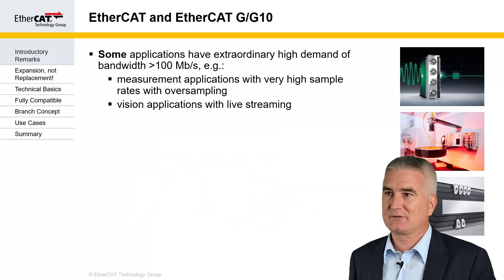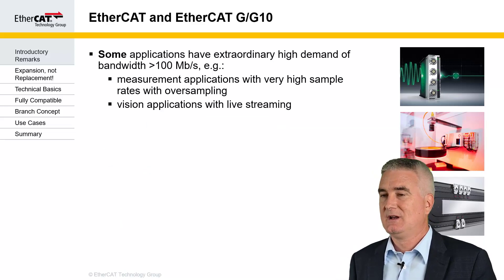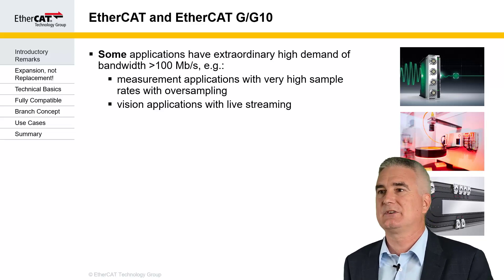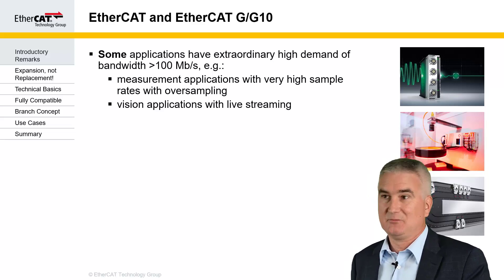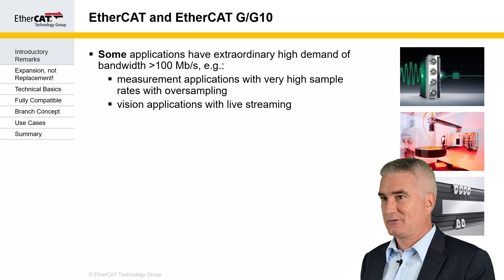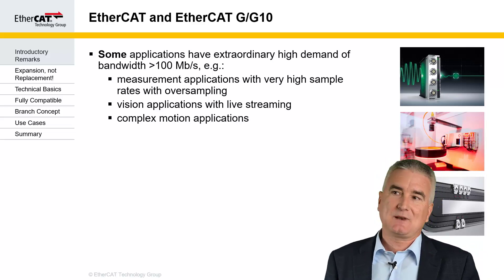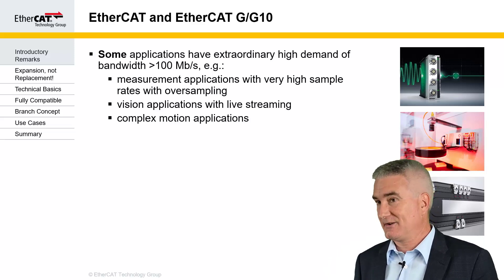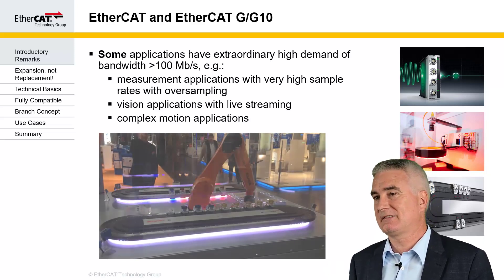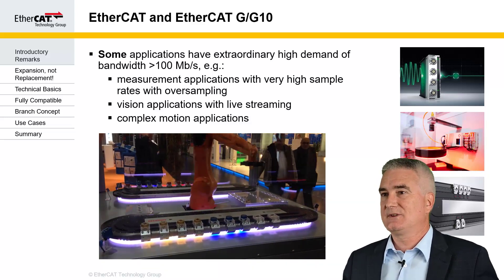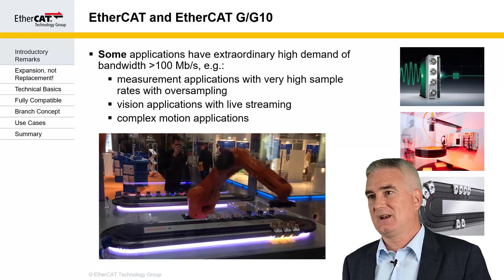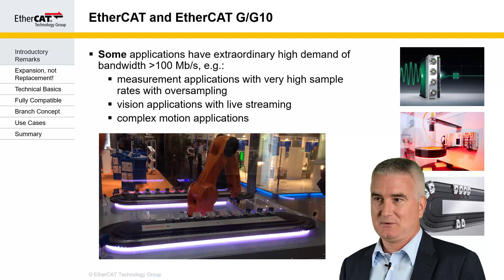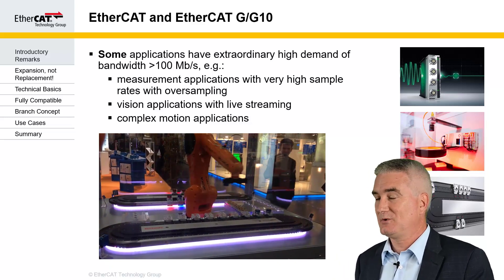Another example is cameras with live streaming. If you have a smart camera which does the image processing inside the camera and just reports the result of that image processing over the fieldbus network, you don't need a lot of bandwidth. But as soon as you start streaming video over the network, you need a lot of bandwidth. Then there are complex motion applications that require a lot of bandwidth. One example is the Beckhoff XTS system, where 3 meters of that transport system requires 64 megabit per second net data throughput. If you have a long system like that, you need multiple EtherCAT networks to handle this, or you need more bandwidth.